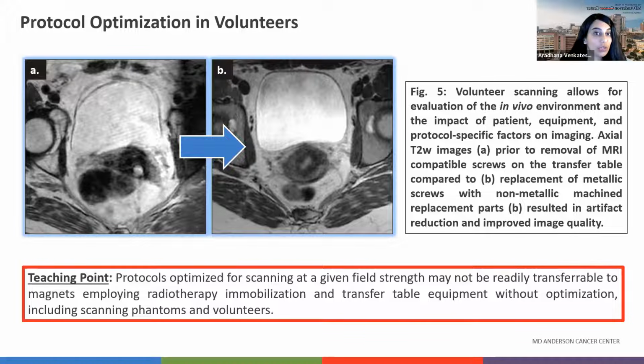This was in fact due to the presence of MR compatible metallic screws on the sides of our transfer table, which, while MR compatible and able to be brought into the MRI environment, reduced our image quality because they imparted increased magnetic field inhomogeneity. So we removed those screws. We were able to replace those with non-metallic machined replacement parts. And as a result, with the replacement of those screws, we were able to resolve the artifact present on the imaging and subsequently screen and image patients without incident.